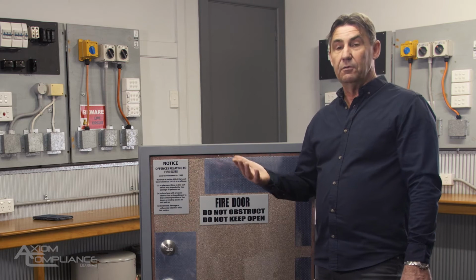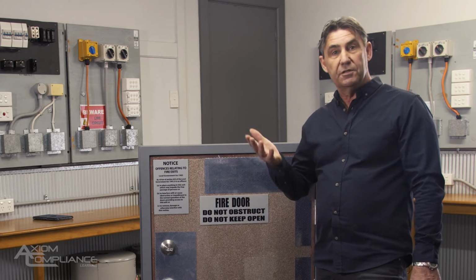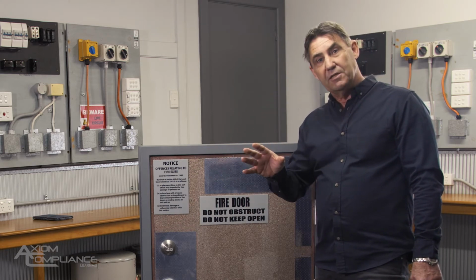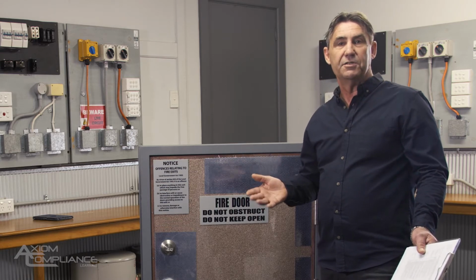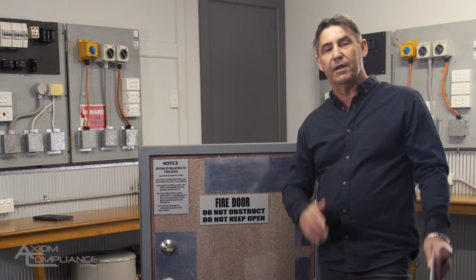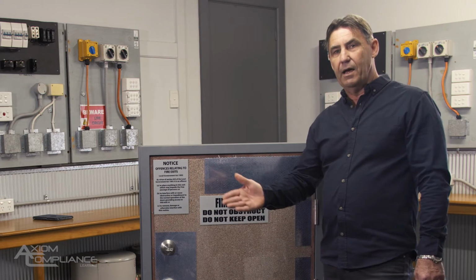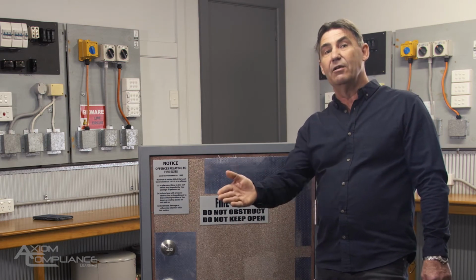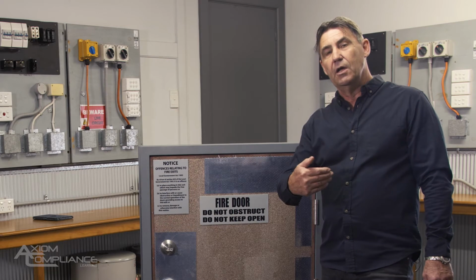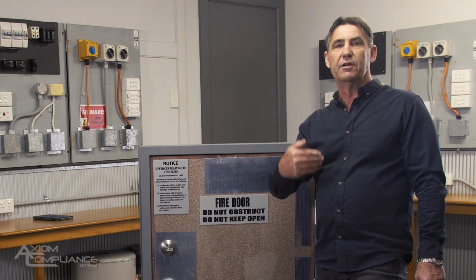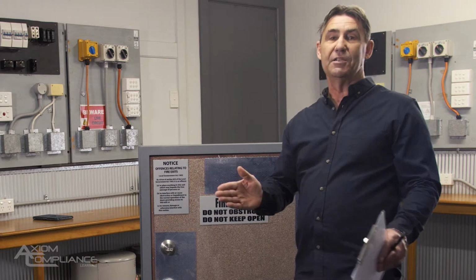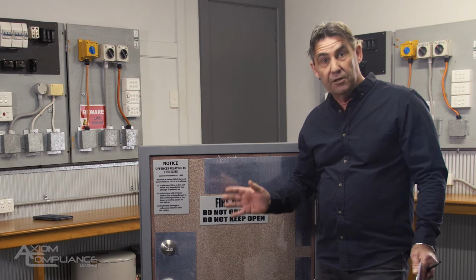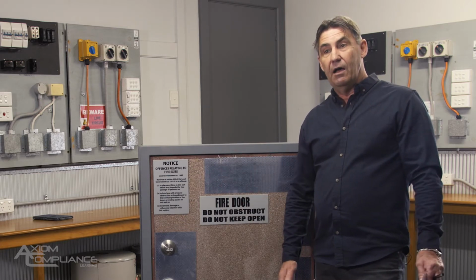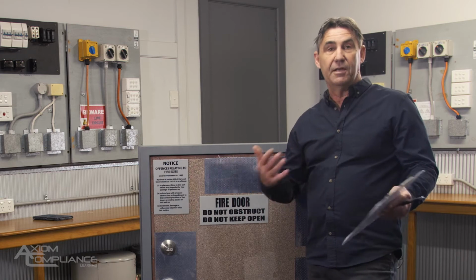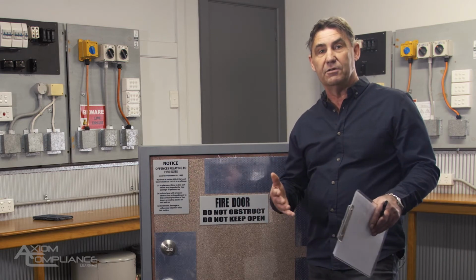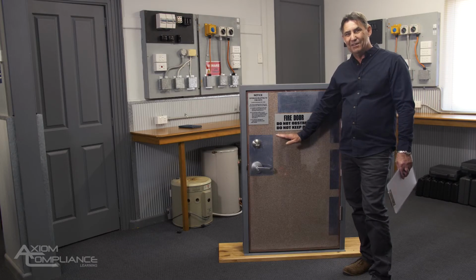For example, if you had a block of units and each of those units were fire separated, or even in a motel situation where each room was fire separated from another room, then the fire door would be a part of the egress system, but it would only be out into a corridor. It wouldn't be the point of egress into an open space to egress the building. So you can also use fire doors for cupboards and other places around the building that are required to be fire resistive. And so the signage is different for those areas.